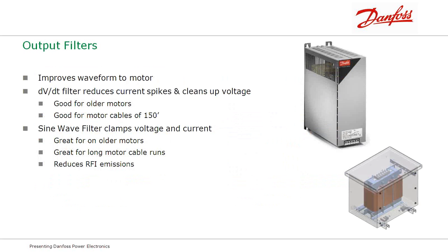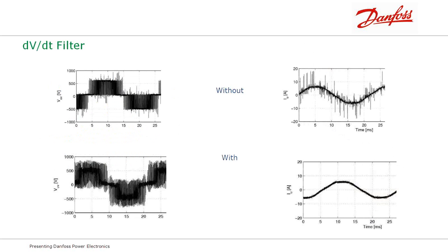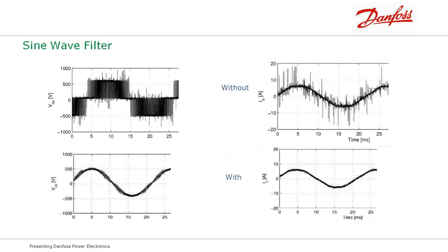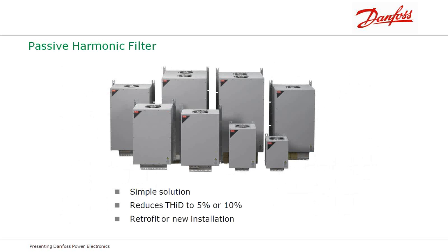Continuing with the output filters, we have a huge selection of output filters, dV/dt filters, which really suppress the current spikes that the drive sees, the motor sees by the output of the drive, suppressing the voltage and the current. The sine wave filter goes one step further and really cleans up the voltage and makes it look very sinusoidal, taking out the noise and the dV/dts and bearing currents and RFI and other things generated.